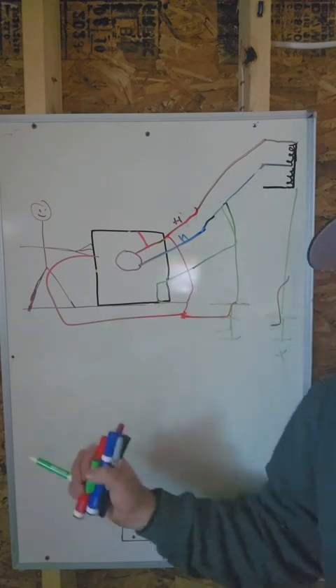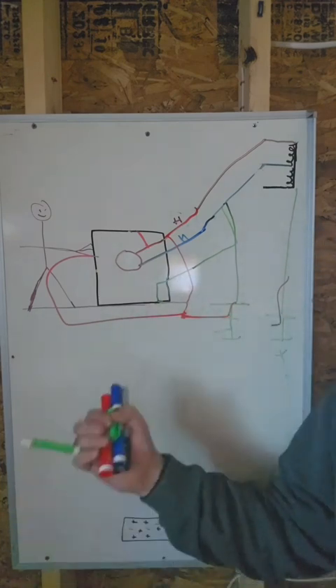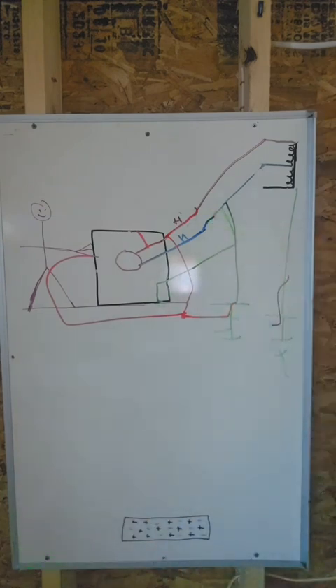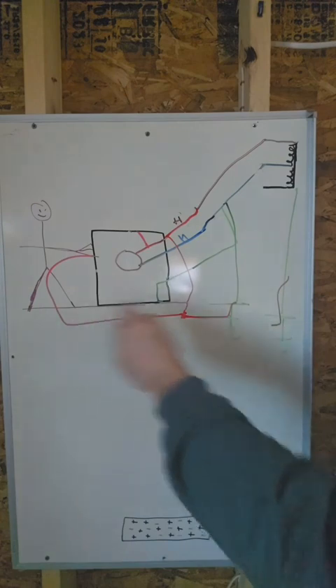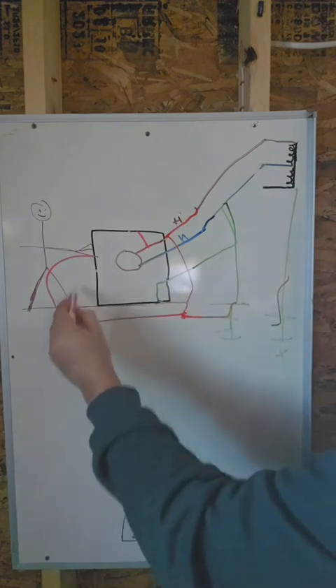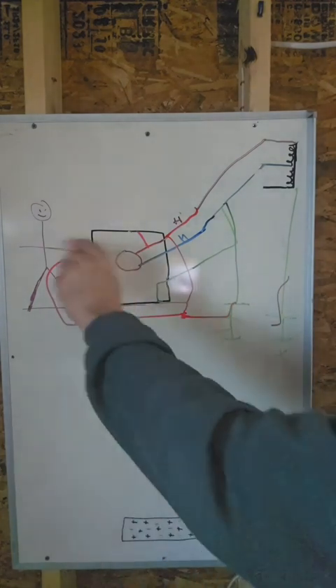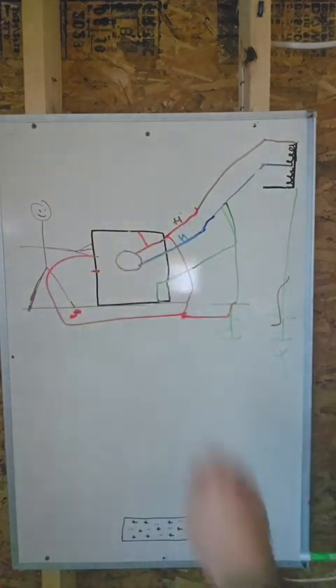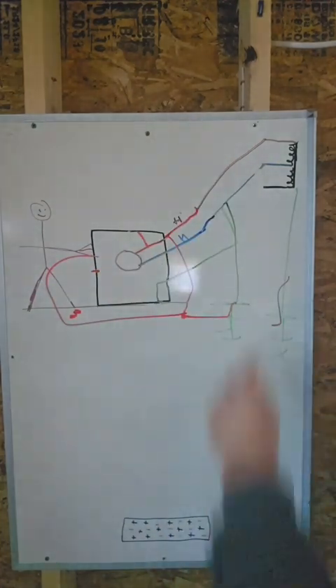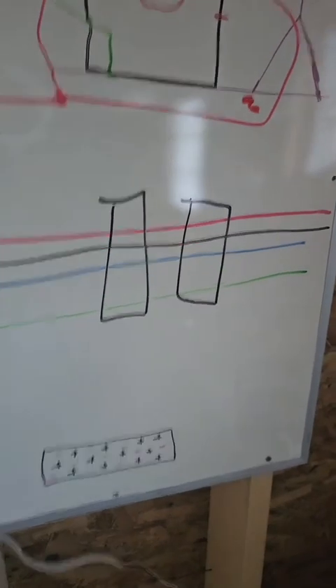Generally, when you have the connection through earth, it's not enough of a flow or a low enough resistance to open the breaker the way the connection straight to your casing is, but it is enough to remove any differences between this dirt and that casing. So the shock hazard is removed if the soil had electricity coming into it from the transformer. Now this is what it ends up looking like.